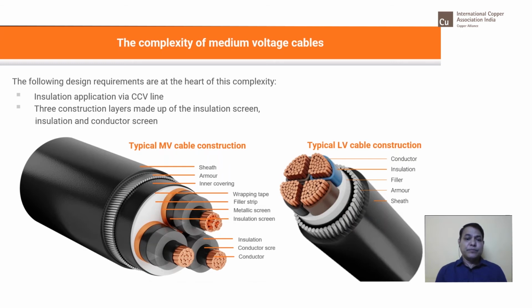In medium voltage cable, you can see there are three layers as the insulation, which is a triple extrusion. The layer of the insulation is quite thick. Over the conductor, a semiconducting screen is put to reduce the stress on the surface of the conductor, and for the insulation from the inner part of the insulation. Plus, over the insulation, there is an insulation screen.